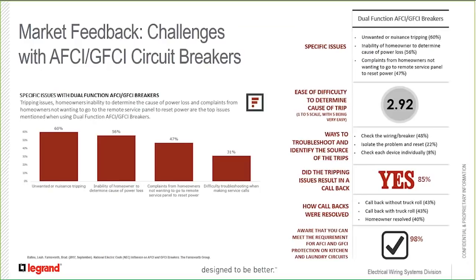56% of them had homeowners that had difficulty determining the cause of power loss. 47% received complaints from homeowners not wanting to go to remote service panels to reset power. And finally, 31% had difficulty troubleshooting when making service calls. On the right here, the thing that stands out the most is contractors using dual function AFCI, GFCI circuit breakers experienced nuisance tripping that resulted in a callback 85% of the time. So these are issues that need to be uncovered and need to be talked about.